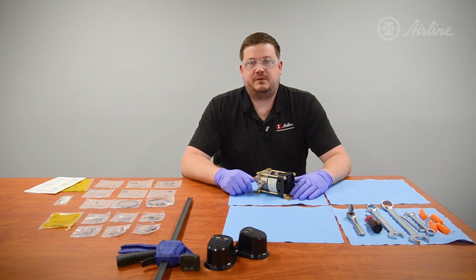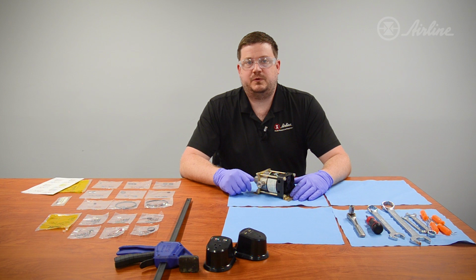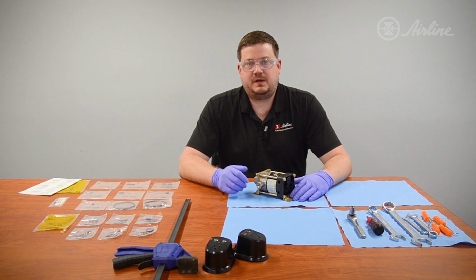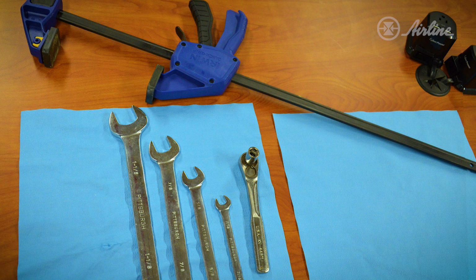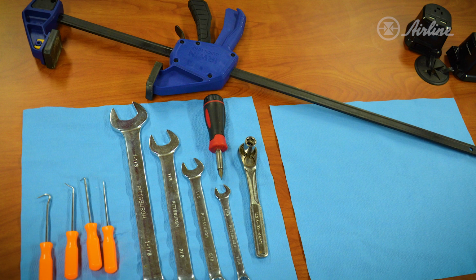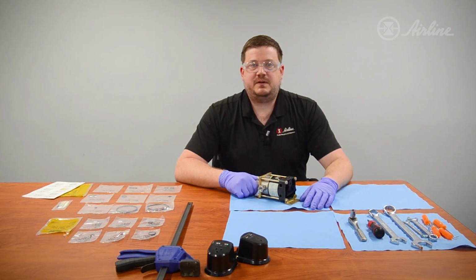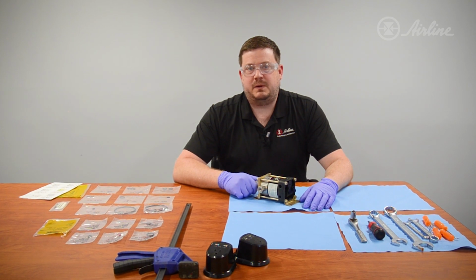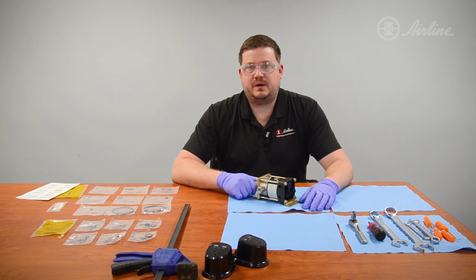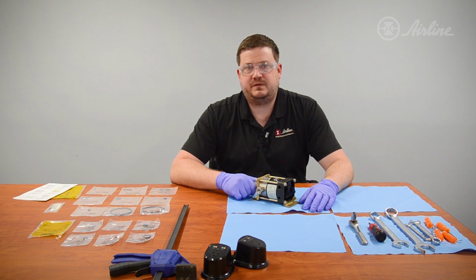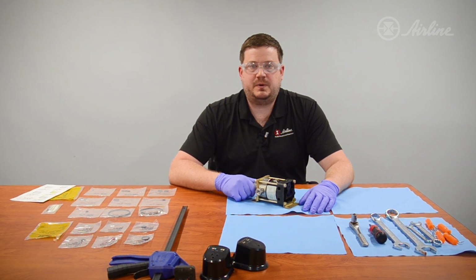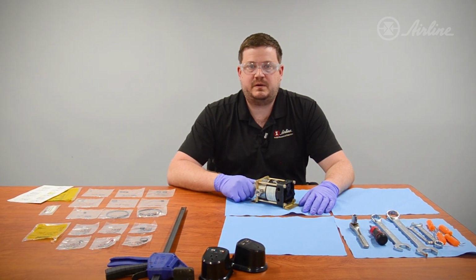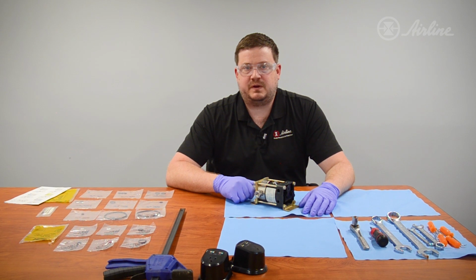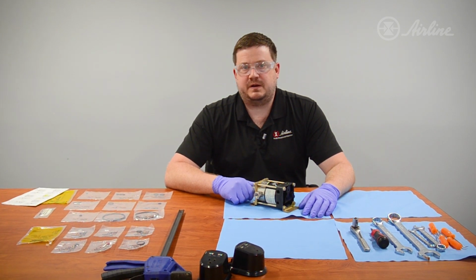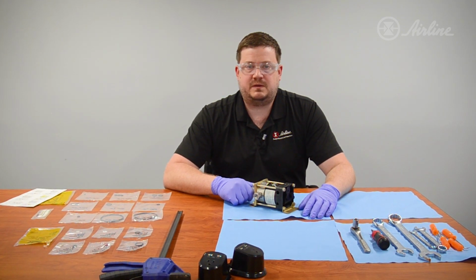Once you have your seal kits and drawing, you'll need a few more tools for the rebuild. You'll need safety glasses, some gloves, a bar clamp, wrenches, a socket set, screwdrivers, and a set of picks. You can see I have a clean work area with the pump, tools, drawing, and seal kits within arm's reach. I find it's good practice to open all the seal kits before getting started, but keep all the components in their individual bags. There are a lot of different O-rings, and we don't want to get them mixed up.